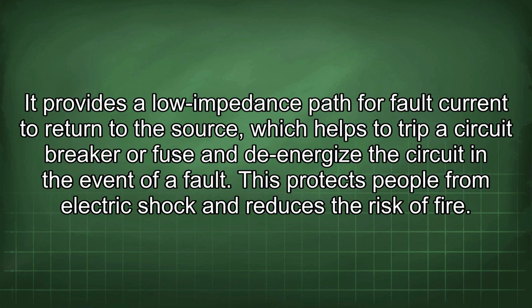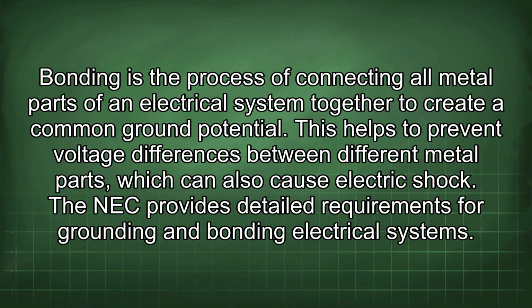It provides a low impedance path for fault current to return to the source, which helps to trip a circuit breaker or fuse and to de-energize the circuit in the event of a fault. This protects people from electric shock and reduces the risk of fire. Bonding is the process of connecting all metal parts of an electrical system together to create a common ground potential. This helps to prevent voltage differences between different metal parts, which can also cause electric shock.